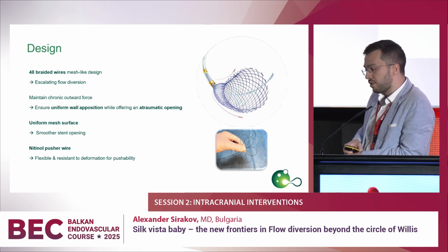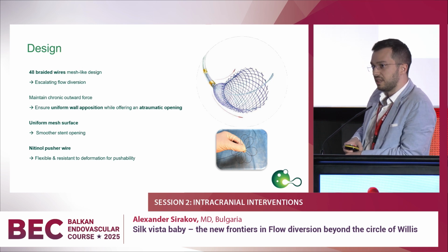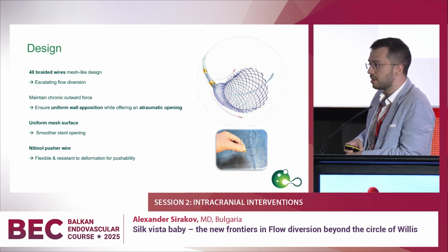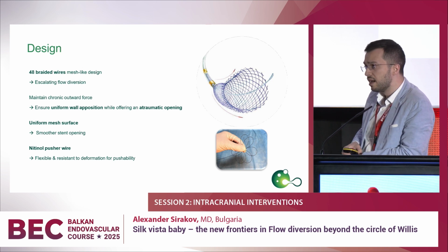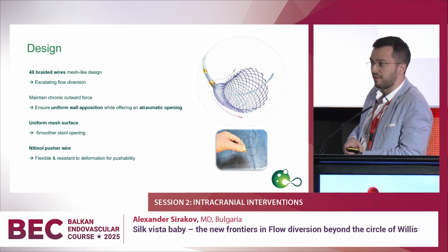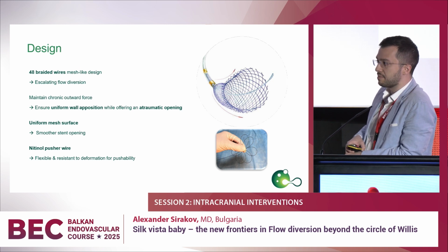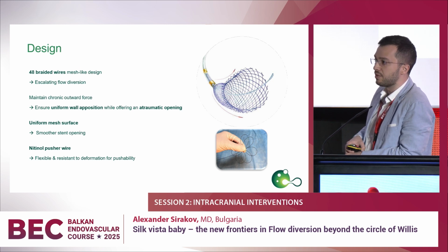The design is notorious. I think we are all aware of the design. It's a DFT technology that binds 48 wires into a very stable mesh. Despite the fact it's made of a DFT technology, it is relatively stable with a good radial force that ensures adequate wall apposition in the majority of the cases. Something that I'm extremely big fan of in this device is the pusher wire. It's made out of nitinol and it's extremely kink resistant.